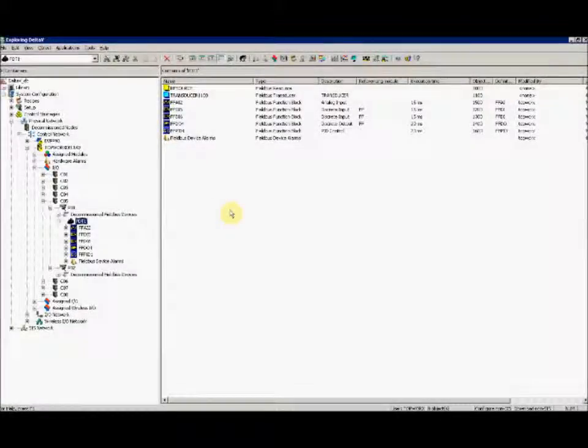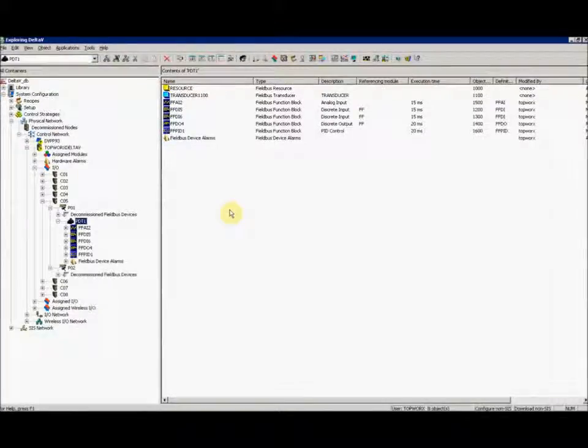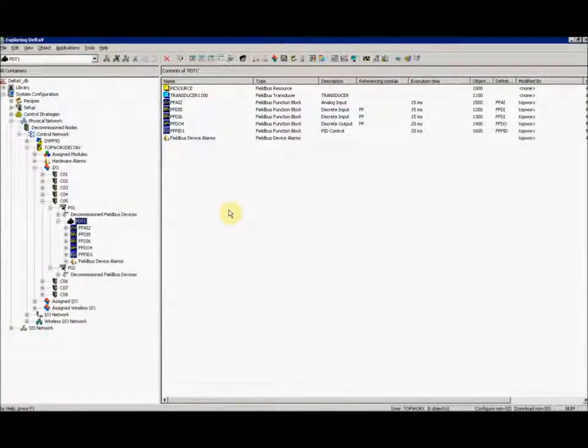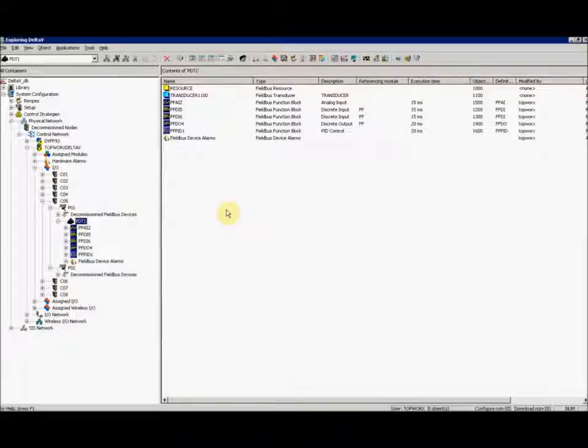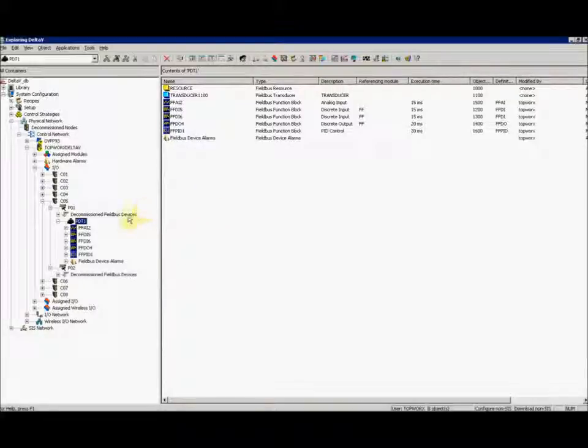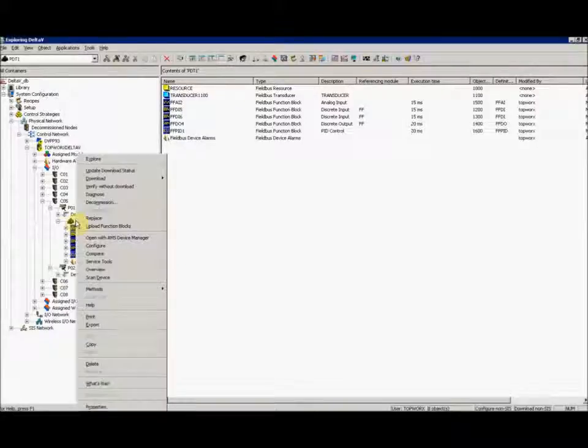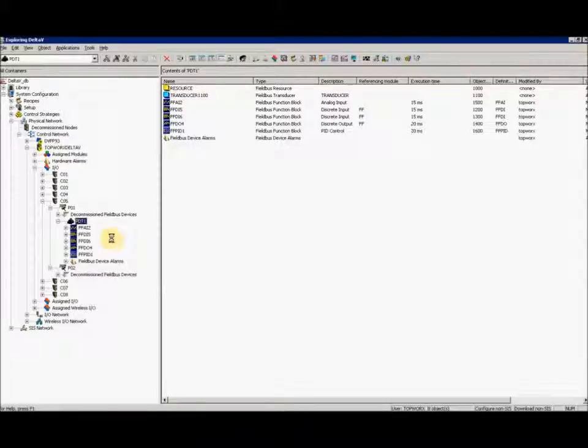To calibrate the device, there are a few different methods. You can do it locally with the button board by removing the lid to the device, with an Emerson 375 or 475 handheld, or through AMS in Delta V. To start off in AMS, right click on your commissioned device and select open with AMS device manager.